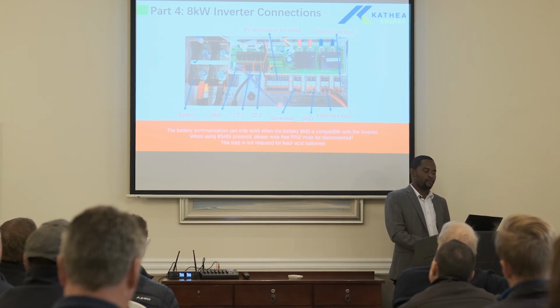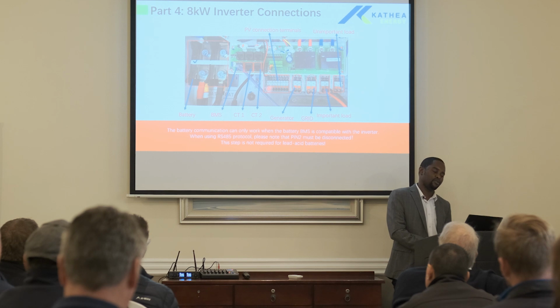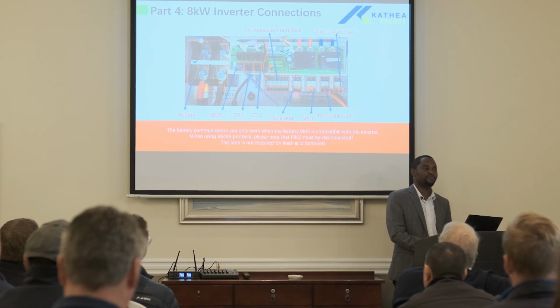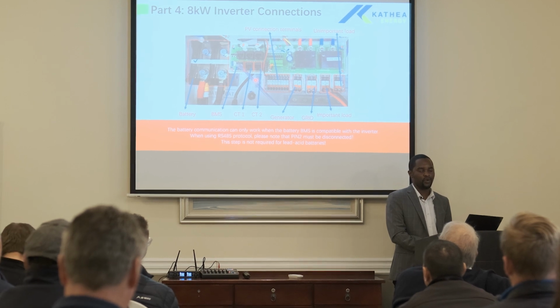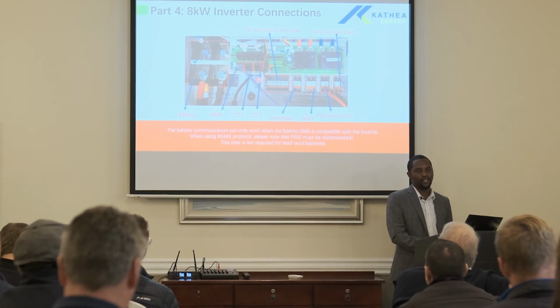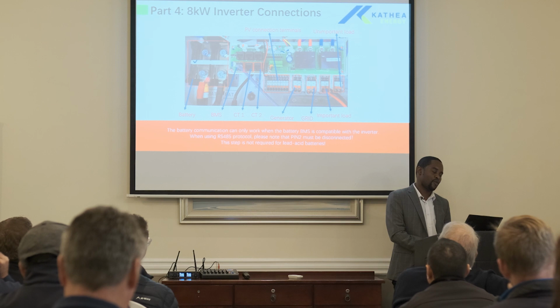If you make a mistake and reverse polarity on the strings, you get an alarm. You don't damage the inverter. Of course, no one wants to do it deliberately, but if you make a mistake, then at least you've got a second chance on the strings. So what it means, in short, is try to pay more attention when you're on the batteries.